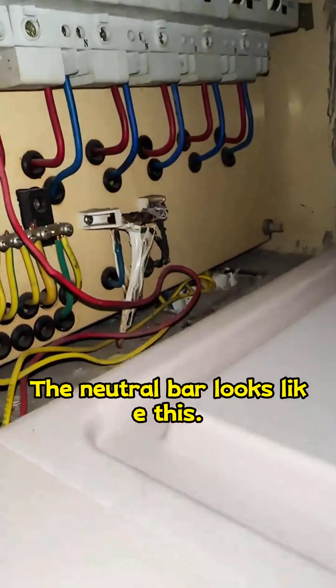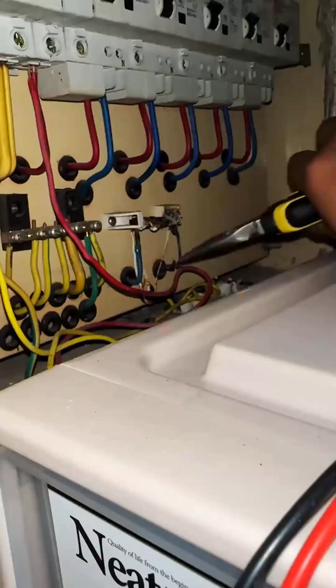The neutral bar looks like this. The entire neutral bar has melted. Loose connections on the neutral wire will overheat. Loose connections can generate high temperatures. This causes poor contact.